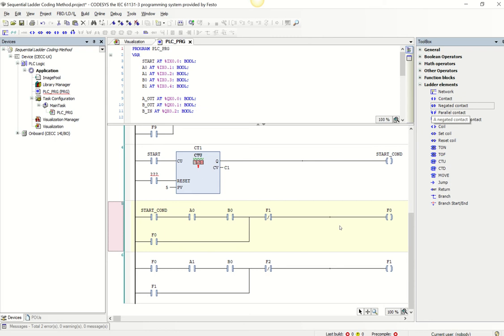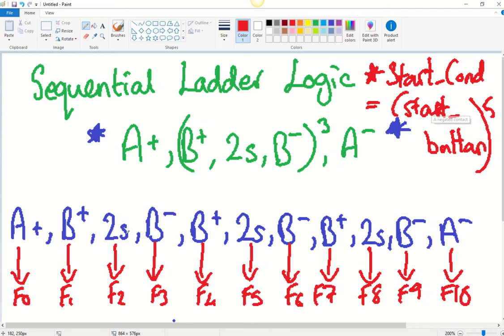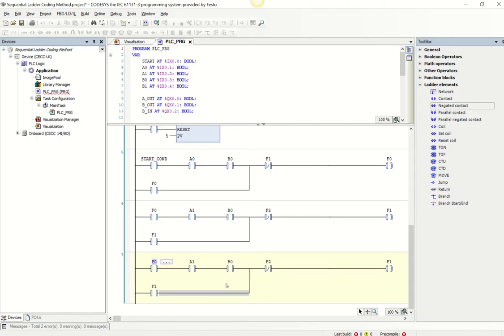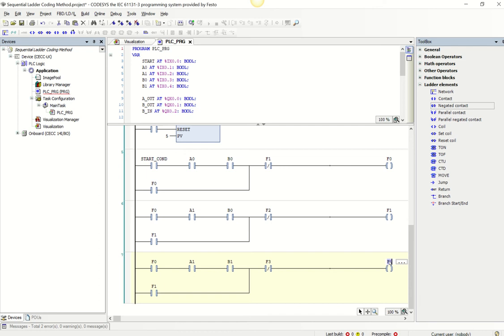You can literally copy and paste the networks down because they all look very similar. A has gone plus, so now B needs to go plus. The contact becomes B1, the step increments — this becomes F2, latched on, and the previous step uses F1. It keeps repeating like that throughout the cycle, just incrementing the flag numbers each time.